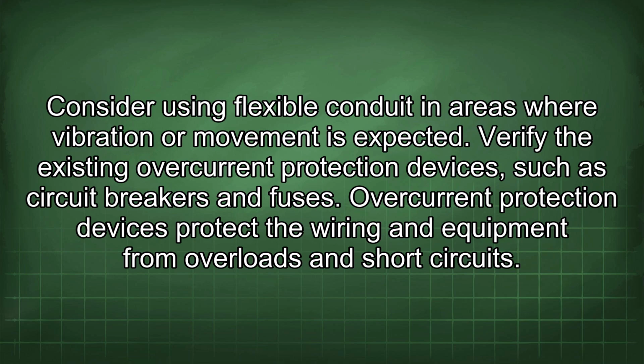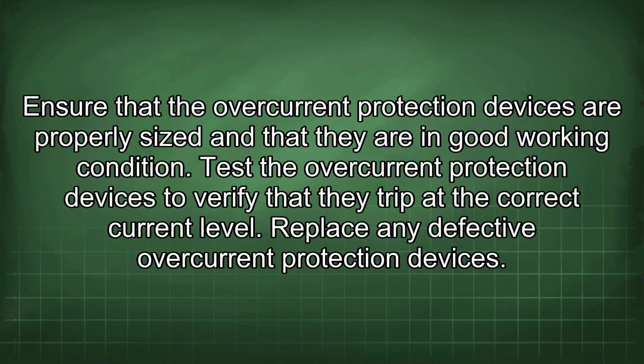Verify the existing overcurrent protection devices, such as circuit breakers and fuses. Overcurrent protection devices protect the wiring and equipment from overloads and short circuits. Ensure that the overcurrent protection devices are properly sized and that they are in good working condition. Test the overcurrent protection devices to verify that they trip at the correct current level. Replace any defective overcurrent protection devices.